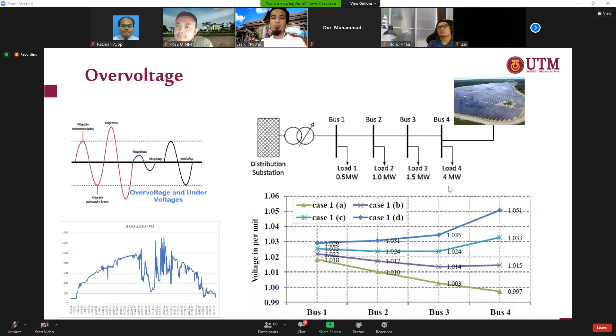So overall, what we can see is that when we have PV injected into the grid, we might have an under voltage problem due to wrongly designed cabling. We might have an over voltage problem, especially during the afternoon if our demand is very low and our generation is very high. During that time, we can have an over voltage problem, and we might have a harmonic problem. I agree that the harmonic from the inverter is very small, around 3%.